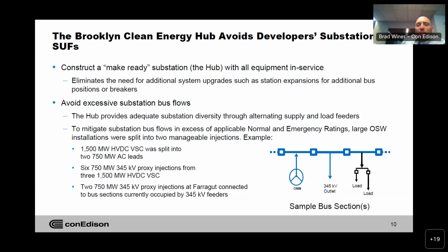The question came in, what regulatory, technical, electrical, and physical specifications will CECONY require for the developer-owned converter stations and their associated lead lines into the Vinegar Hill Make-Ready substation? As part of the interconnection process, Con Edison provides developers with relevant and applicable standards associated with their interconnection. In general, we focus on the interconnection at the substation itself. There's coordination between the standards and specifications of a developer's requirements with, say, the NYISO metering, as well as coordinating with the unique circumstances of a particular substation. We do not, however, get specifically into giving direction or requirements outside of those things that could have coordination concerns on a developer's design with their cables and converter stations. We have in the past, and will continue, to provide input when asked, based on our knowledge and experience and understanding of the subsurface 345 and 138 kV systems.